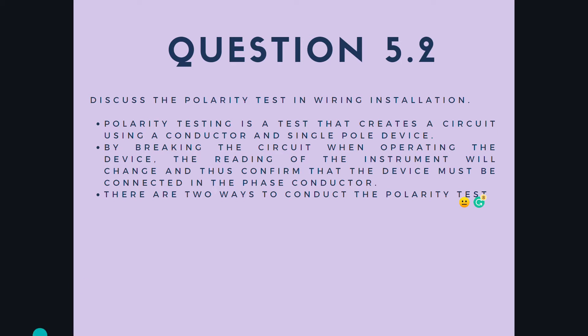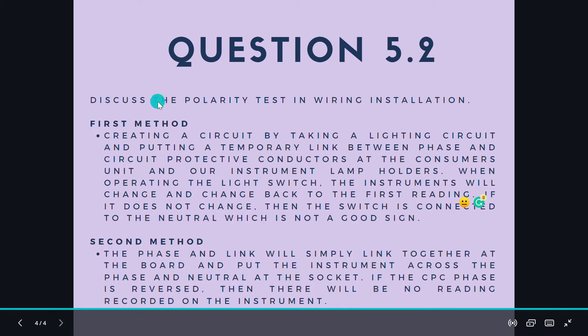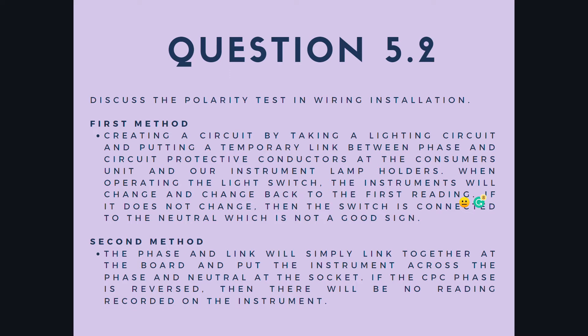There are two ways to conduct the polarity test. The first method is by creating a circuit, taking a lighting circuit and putting a temporary link between phase and circuit protective conductors at the consumer's unit and the instrument lamp holders. When operating the light switch, the instrument reading will change and change back to the first reading. If it does not change at all, then the switch is connected to the neutral, which is not a good sign.